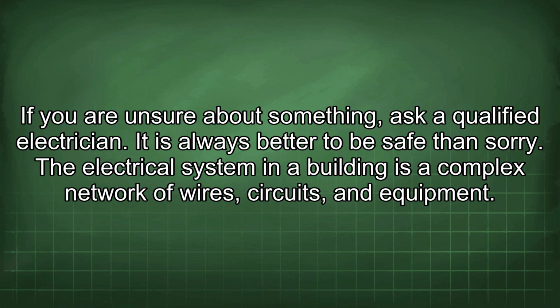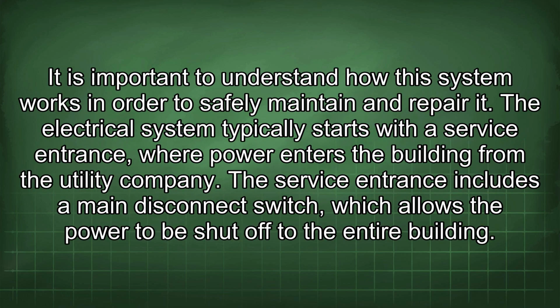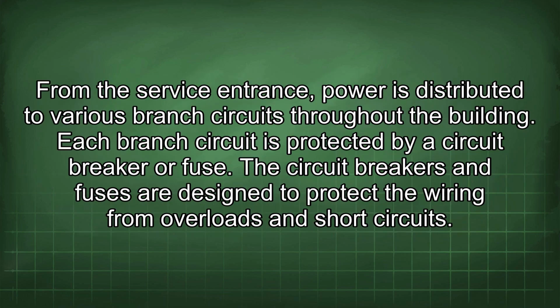The electrical system in a building is a complex network of wires, circuits, and equipment. It is important to understand how the system works in order to safely maintain and repair it. The electrical system typically starts with a service entrance, where power enters the building from the utility company. The service entrance includes a main disconnect switch, which allows the power to be shut off to the entire building. From the service entrance, power is distributed to various branch circuits throughout the building. Each branch circuit is protected by a circuit breaker or fuse. The circuit breakers and fuses are designed to protect the wiring from overloads and short circuits.